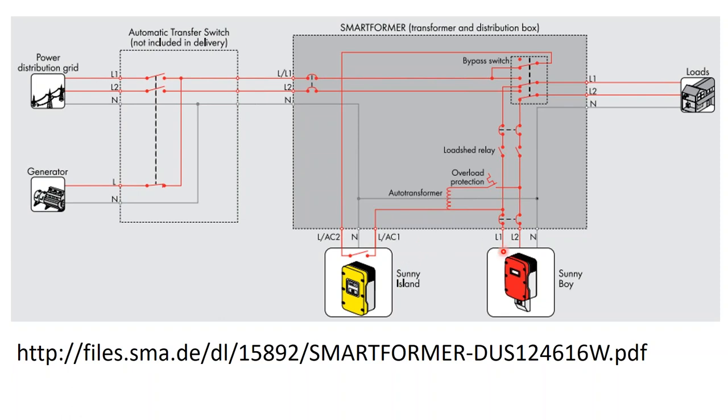Down the road, what we'll do is install a separate inverter for the battery system. Because we're using an SMA batteryless inverter, and SMA has a battery inverter, the two inverters can communicate together in an intelligent manner. Most of you are going to want that. Most of you are going to want to use the same manufacturer for the battery and the solar array, because instead of powering down the array when the batteries are full, it can keep the solar array on but throttle back the solar array output. And so whatever the building load is, it's still running off the solar array.